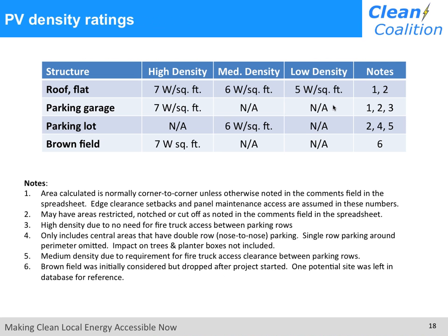I'm going to get a little bit into some details here on how we rated and how we calculated the amount of solar per site. So we used a density rating. We looked at each site and gave it a rating based on whether that site could have high density of solar panels, medium density, or low density, depending on the clutter that was on that rooftop or how the parking lot was arranged. We have a density rating for parking garages that is high because on parking garages, essentially, there's no need for fire truck access between parking rows, for example.